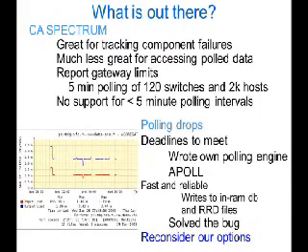They've used Spectrum for 10, 20 years now. They're quite happy with it. It really is good for tracking component failures. We discovered very quickly, however, that it takes all of the data, stores it very well, and then hides it from you. Even at fairly low polling intervals of about five minutes, the report gateway is already a problem. If we have a drop for any time, we have to wait for the system to catch up just to find out what's been going on. And there's no support at all if we want to poll at less than five-minute intervals.